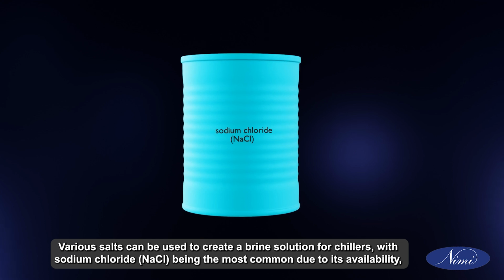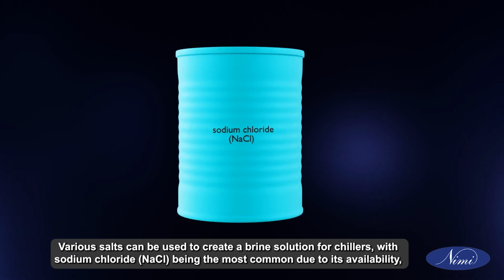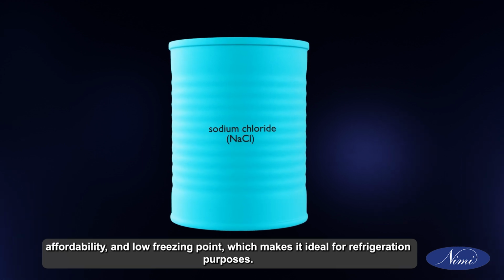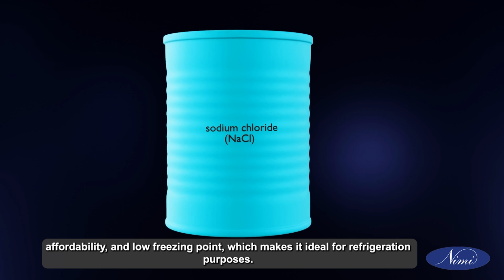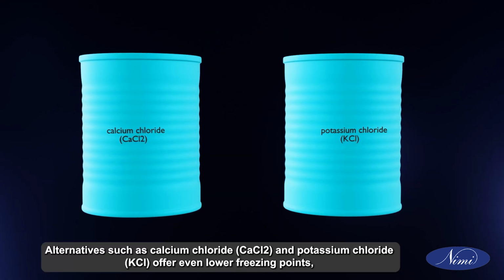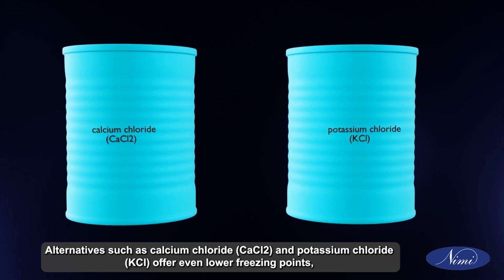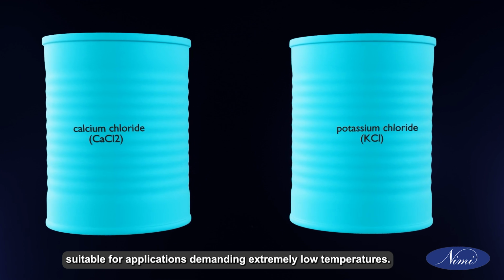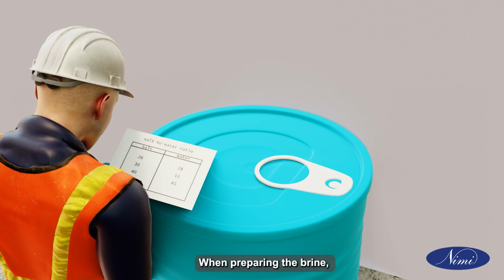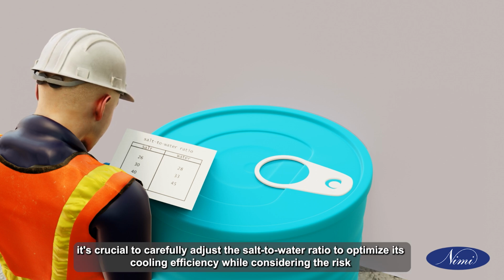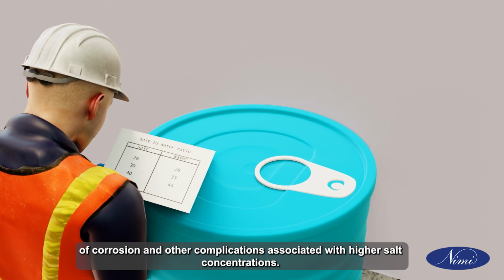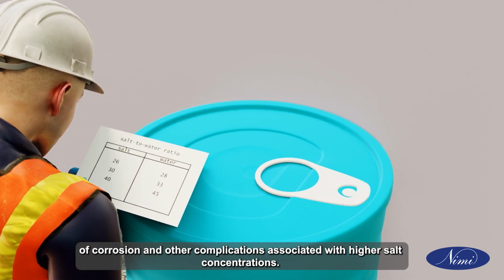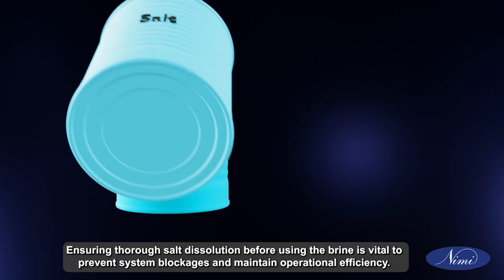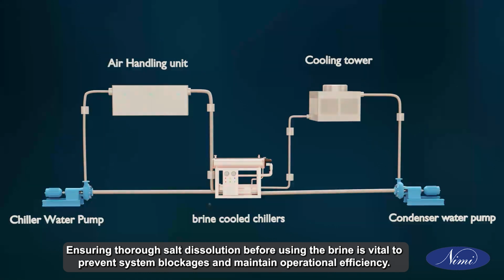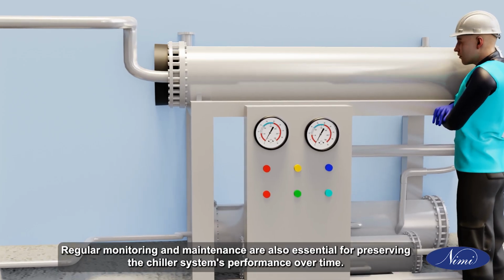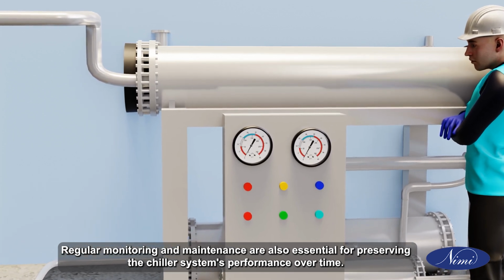Various salts can be used to create a brine solution for chillers, with sodium chloride, NaCl, being the most common due to its availability, affordability, and low freezing point, which makes it ideal for refrigeration purposes. Alternatives such as calcium chloride, CaCl2, and potassium chloride, KCl, offer even lower freezing points, suitable for applications demanding extremely low temperatures. When preparing the brine, it's crucial to carefully adjust the salt-to-water ratio to optimize its cooling efficiency while considering the risk of corrosion and other complications associated with higher salt concentrations. Ensuring thorough salt dissolution before using the brine is vital to prevent system blockages and maintain operational efficiency. Regular monitoring and maintenance are also essential for preserving the chiller system's performance over time.